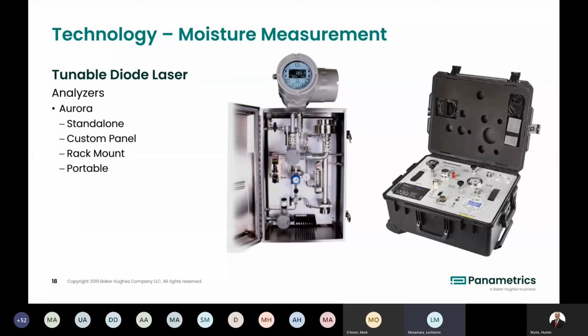So it's very easy to do. You shut off your process, and make sure it's safe, that there are no hazardous gases, before you open up the absorption cell. Using the maintenance kit that comes with the Aurora, you can take the flange off the bottom of it, look at the mirror, and clean it, just using lens tissue and some acetone. Then you can reinstall it, purge with nitrogen for an hour or two, and be back up and running in a couple of hours. So that's the one we've seen the most, I think, generally process related.